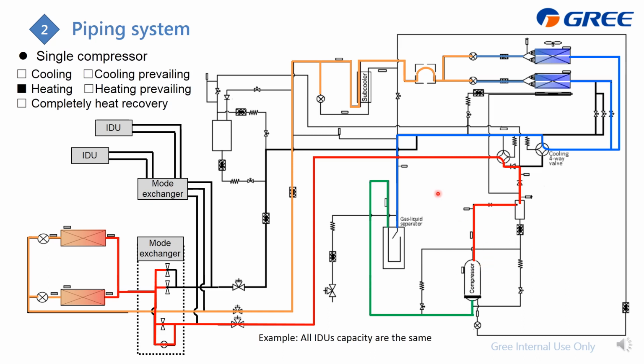If we detect the outdoor ambient temperature is low, then we need to use the EVI, and also just like what I had introduced before, the refrigerant will get through this subcooler EXV and then become gas, and then we just inject this gas to the compressor to raise the heating performance. And also at this time, even if there is no requirement from the low pressure gas pipe, we still collect the low pressure just like this. And also the same for the other 2, even if they are not working.